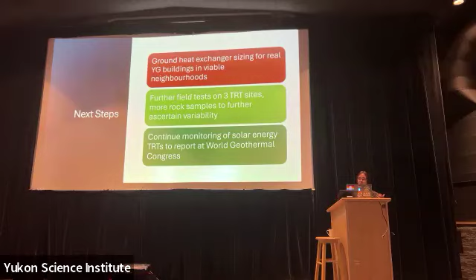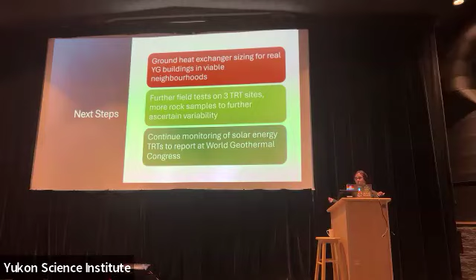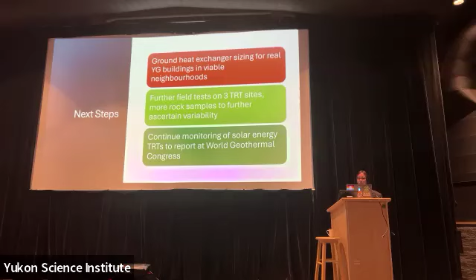They would be really beneficial paired with biomass, for instance - you could have a boiler fed by a ground heat exchanger most of the year, and then use a biomass boiler to bump the temperature up in the middle of December when we have a really high load. That would help ensure we're not drawing the ground temperature down too quickly, because that's the risk - if you don't size the system appropriately, you draw the ground temperature down and then have to let it recharge for however many years in order to use it again.